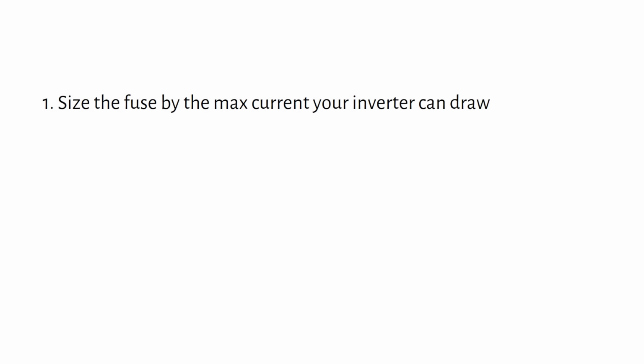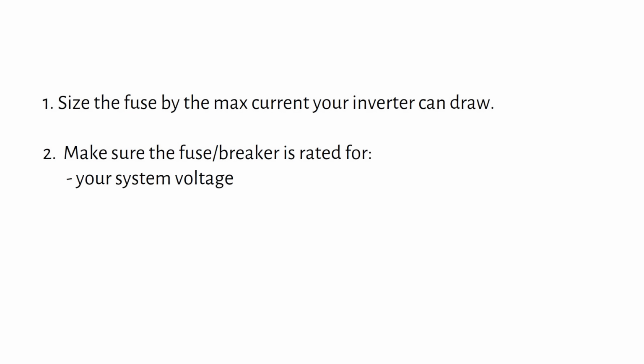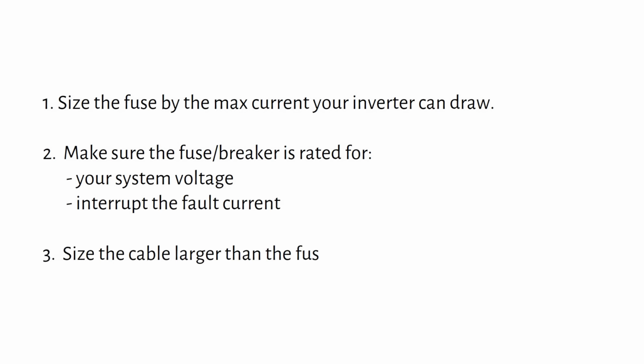So here's what we learned today. Size the fuse by the maximum current your inverter can draw. Make sure the fuse or breaker is rated for your system voltage and can interrupt the fault current. Then size the cable larger than the fuse.